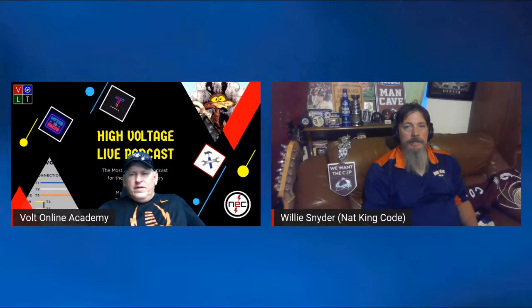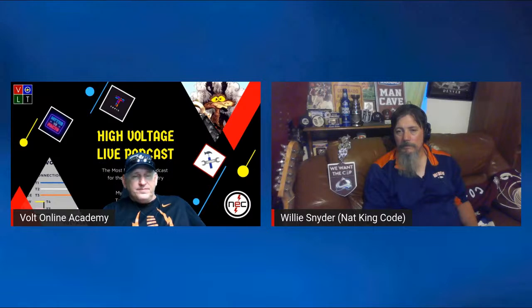But it was Christine Porter, and she's the one that actually gave me that interpretation that if you have a smaller size than the actual electrode, then it's considered a bonding jumper. That's right. And that's why all that's been fixed, so they can't argue that point anymore.